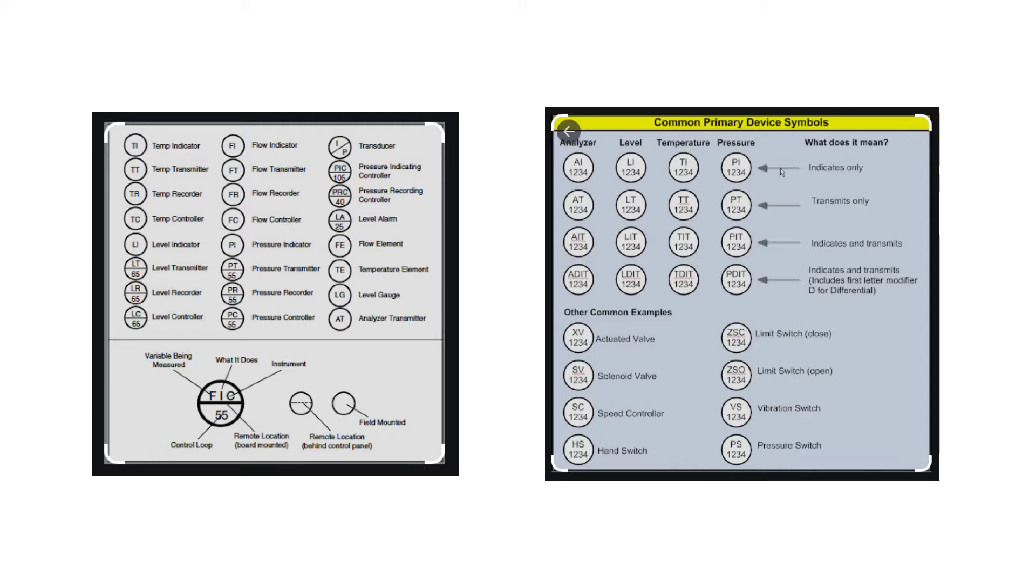So on these P&ID tags you'll see that they can indicate temperature, flow, level, pressure. You'll see other common examples on here of what these different letters and numbers mean. Some indicate pressure. Some also will transmit, like a transmitter. Some will both indicate and transmit as you can see in this key here. And they usually have a control loop number assigned to them. That's the bottom number in the tag.